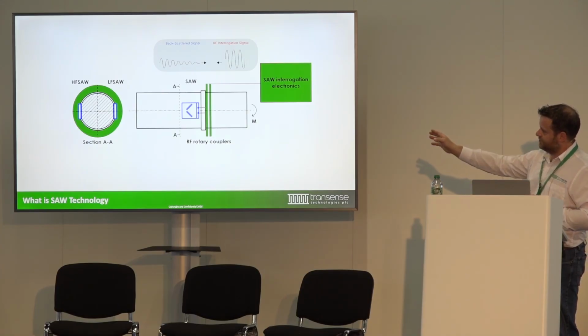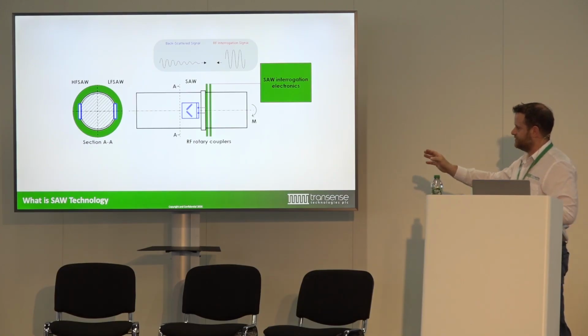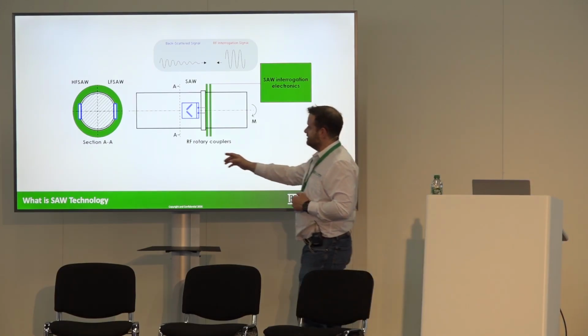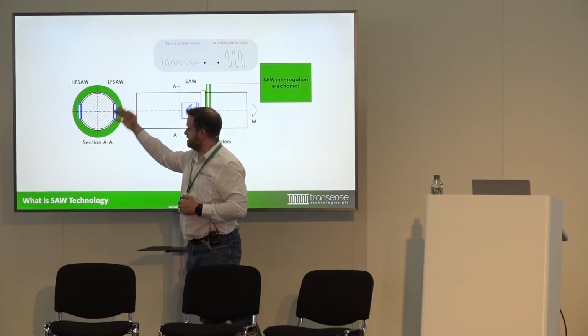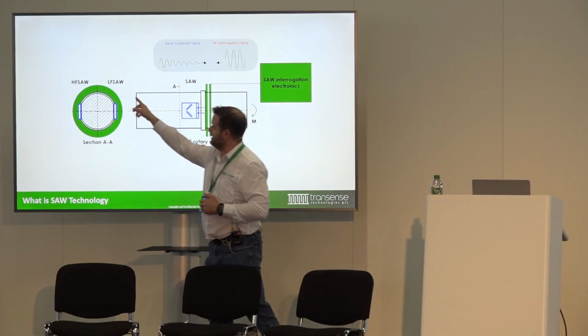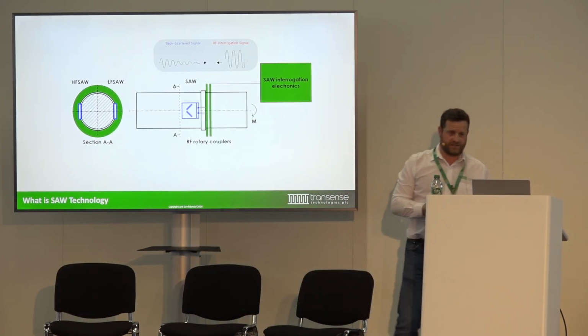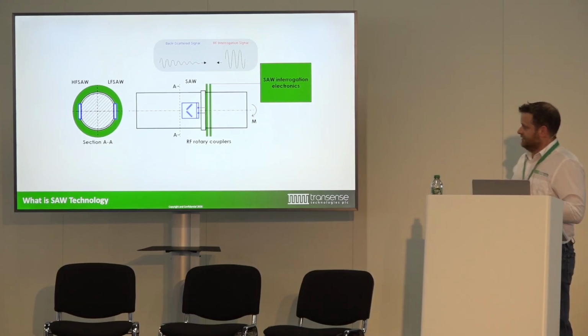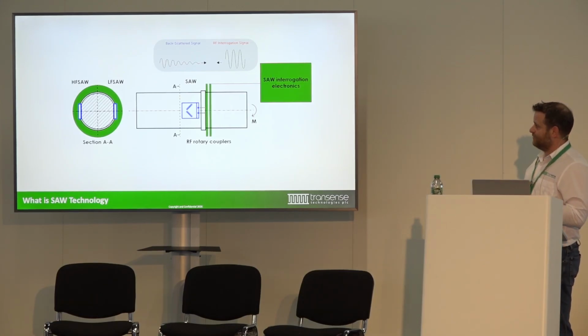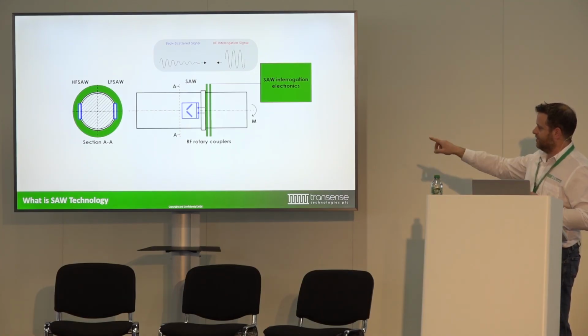We use two sensing elements on the shaft. So what you can see here is a cross section. The two parts are slightly different, so we call them HF and LF - H is high frequency and LF is low frequency. They're pretty similar in terms of the makeup of the parts. In total, between the HF and LF SAW, there's actually 5 individual IDTs on each torque measuring system.